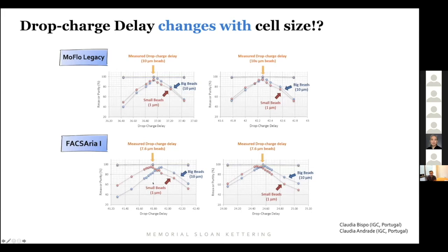Then we look at the ARIA and we were surprised, or maybe not as surprised, because there is a lot of anecdotal evidence saying that jet in air is different from cuvette-based systems. And so this is very tempting to say, oh, there we go. Do you see? One performs better than the other.